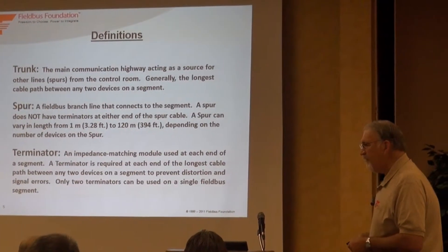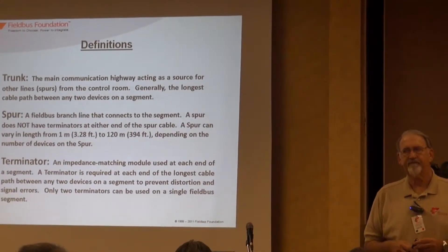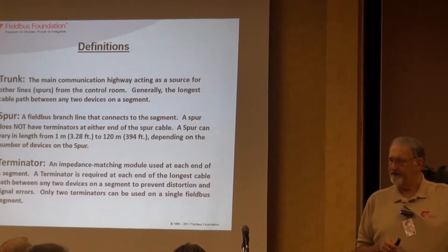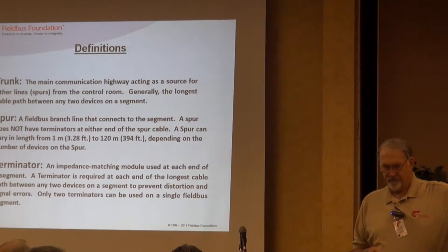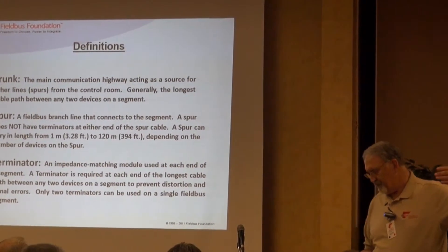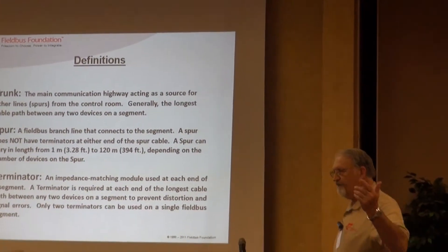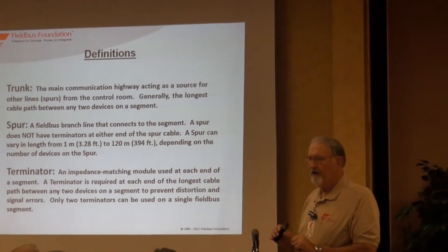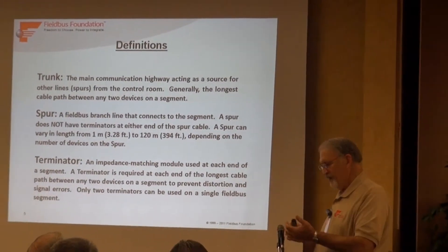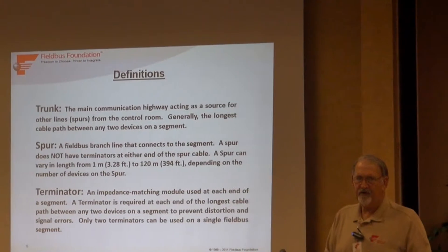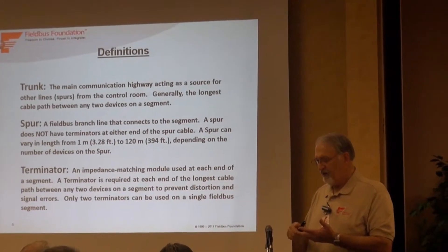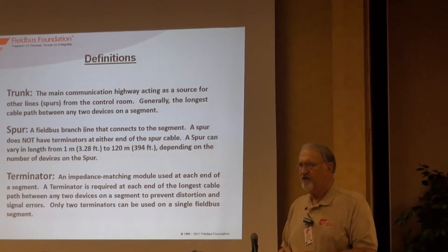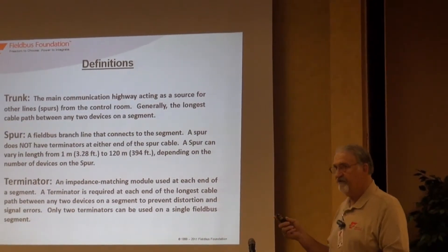A trunk is generally the longest piece of wire - that one pair of wire that usually goes from the H1 interface or linking device or whatever you're using out to the field, and it usually stops at a device coupler. You can have different terms for that. In the old days it was brick, megablock, segment protector, whatever. The generic term is device coupler, and there are registered device couplers now.